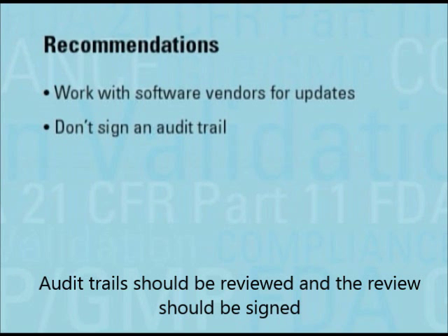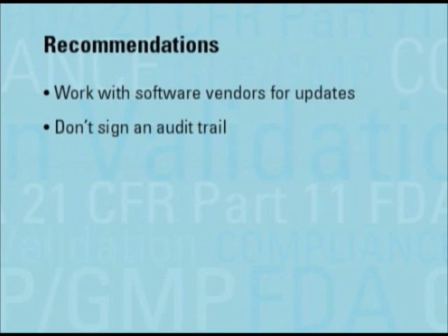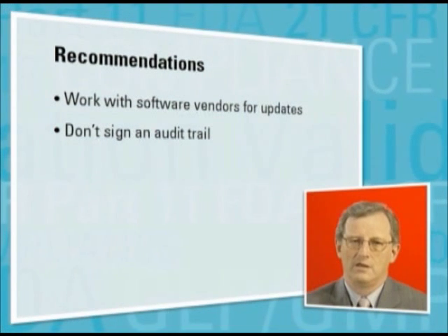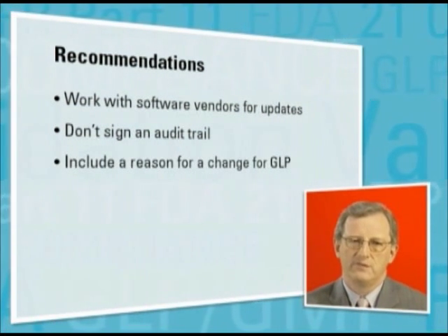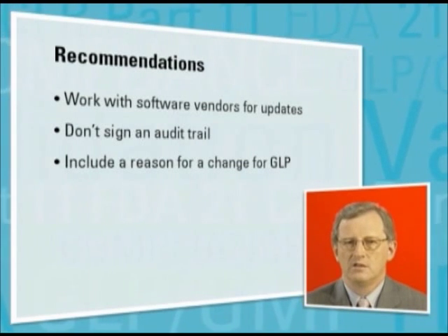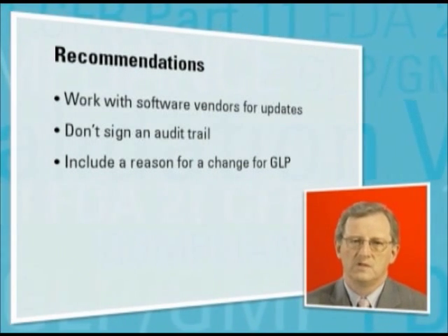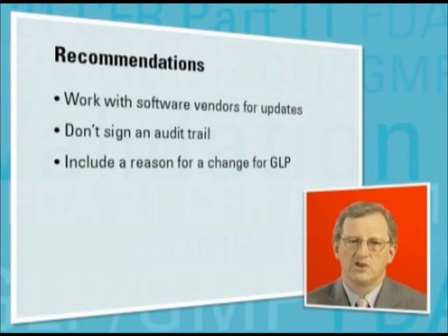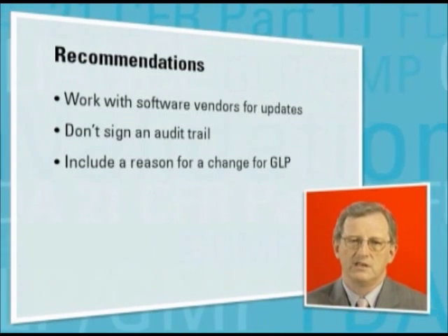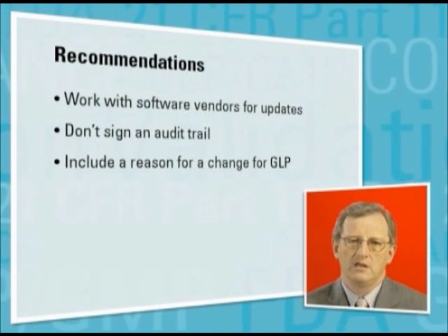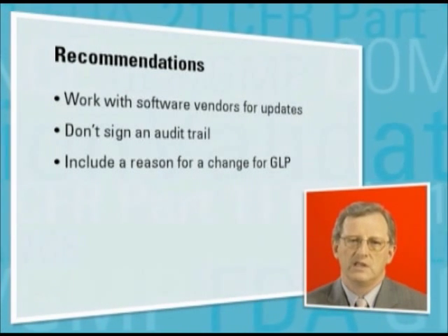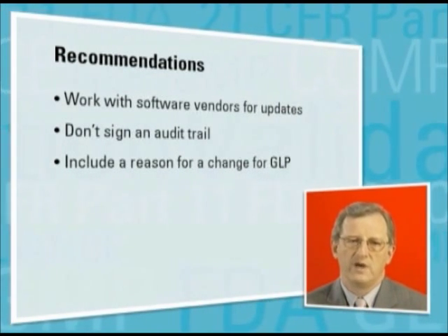The danger is that if a person can sign an audit trail, it is also possible to change or delete part of that audit trail. If you work in a GLP environment, you should enter a reason for the change. This is a software issue. The Agilent ChemStation security software has an entry field for the reason, but you can type just NA for not applicable if the predicate rule does not require a reason.